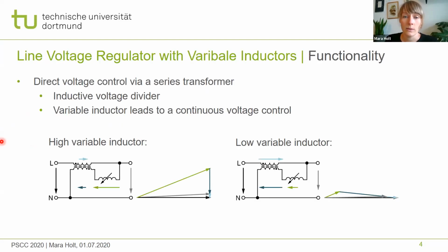Now I'm starting with the working principle and an improved setup we established in previous studies. The elementary structure of the line voltage regulator is composed of a series transformer, whose primary winding is part of an inductive voltage divider, and a variable inductor, which forms the second part of the voltage divider. The inductance of the variable inductor can be reduced, which increases the voltage at the primary winding of the series transformer and its effect on the output line voltage. Depending on the transformer winding direction, voltage boost mode or voltage reduction mode can be achieved.